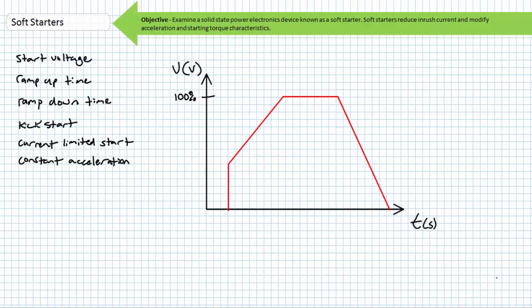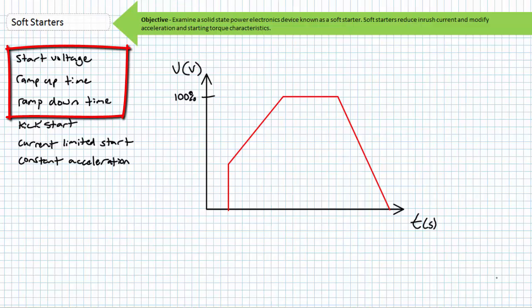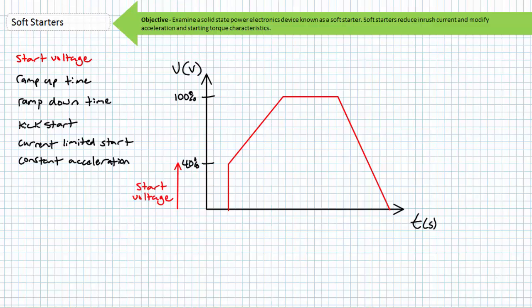Most soft starters have the following user-adjustable characteristics: starting voltage, ramp-up time, and ramp-down time. More advanced soft starters may also include the following additional features: kickstart, current limited start, and constant acceleration. We'll briefly discuss each of these aspects. The starting voltage is ordinarily expressed as a percentage of full voltage. This is the starting voltage at which a soft starter initiates conduction to a motor. Ordinarily, soft starters should avoid going below around 40% of full voltage, since anything less may not produce the current necessary to even move the rotor.